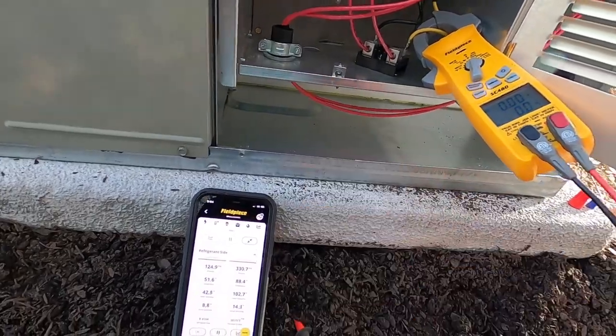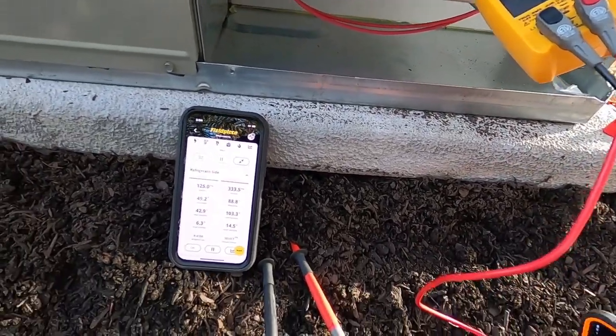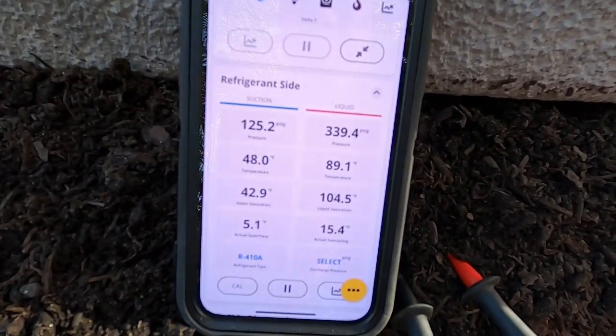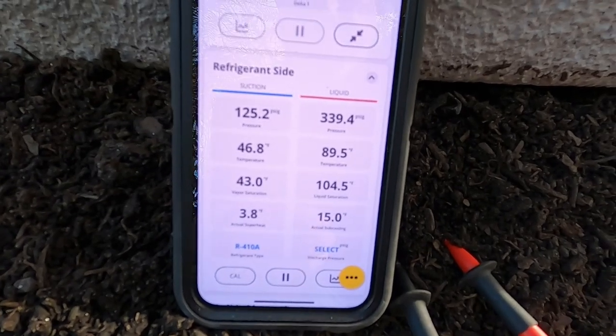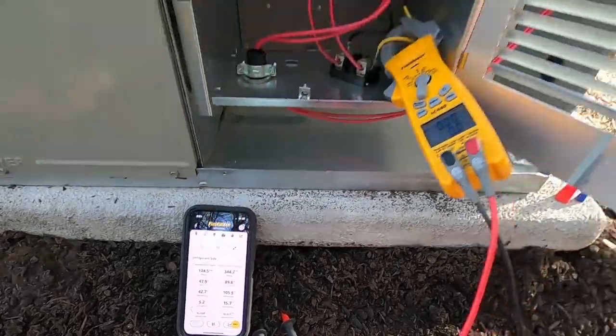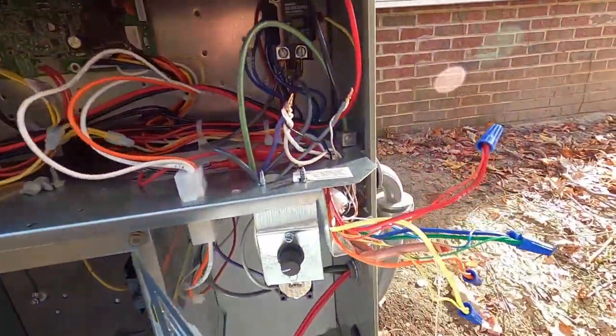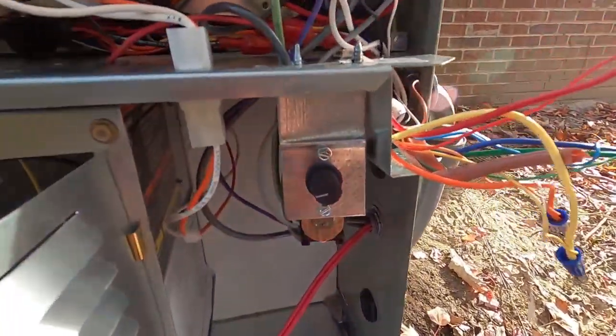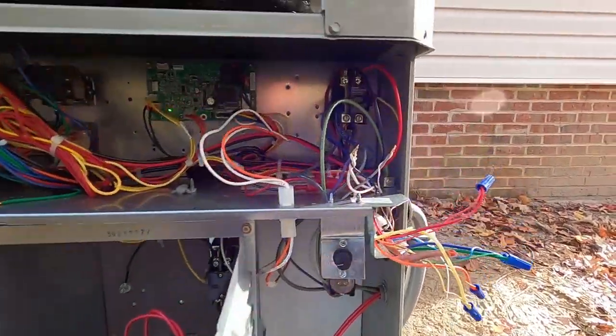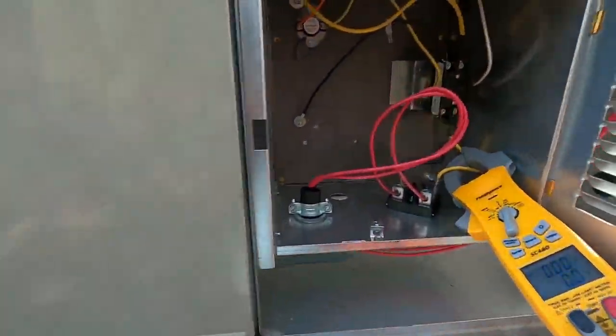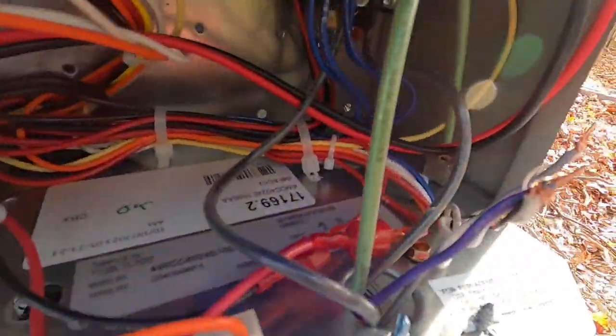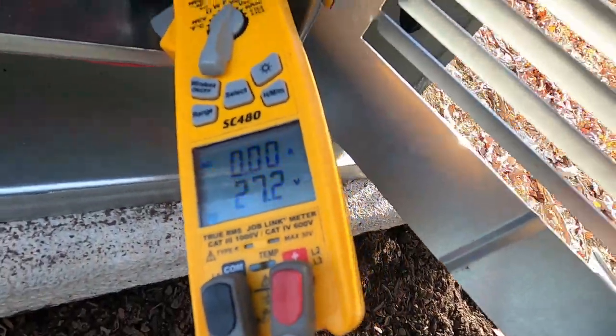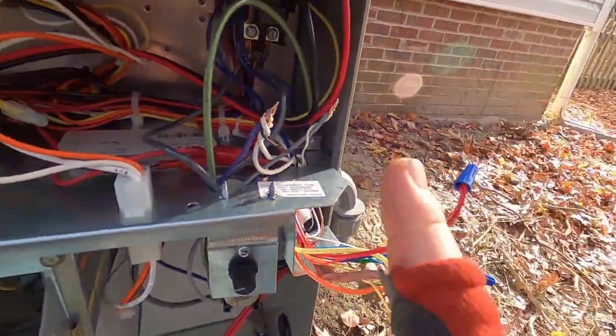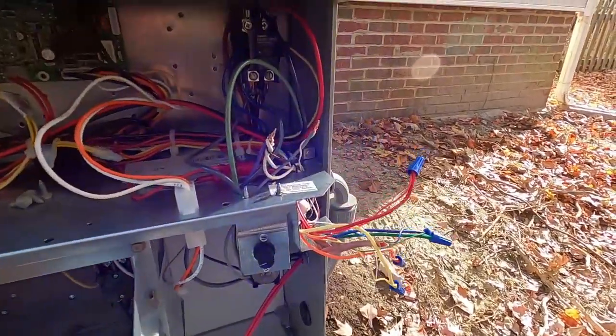Alright guys, so we are now in heat mode, and these are our pressures right now in heating. But keep in mind it's about 67 degrees outside, so those pressures are going to creep right up there, but everything's running. And now this switch is open right now because obviously the temperature outside is above what it's set to. So I do already have a call. I'll show you that real quick. Checking it right there. I do have a call for auxiliary heating to be on, but it's going through this switch. Switch is still open because it's warm outside.